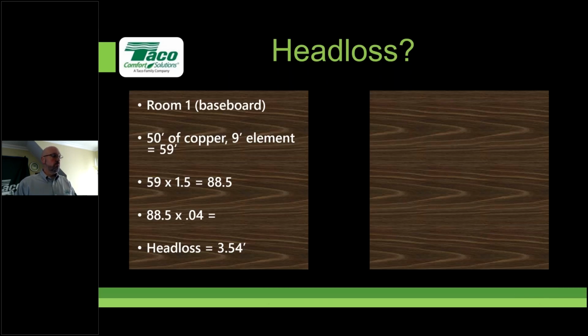So for 3/4 inch copper pipe, the maximum flow rate happens to be 4 gallons per minute. So when we have a 3/4 inch line, we multiply whatever it is by 0.04. We're presuming 4 feet of head at 4 gallons per minute through that pipeline. If the actual flow rate is lower, the real head loss would be lower, which is why this is a very forgiving and very easy formula. It gives you a lot of fudge factor. The same number, 0.04, is applicable to all sizes of pipe because we're estimating at the highest flow rate for each size of pipe, which would be 9 gallons a minute for 1 inch, 14 gallons a minute for 1.25 inches, 22 gallons a minute for 1.5 inches, etc.